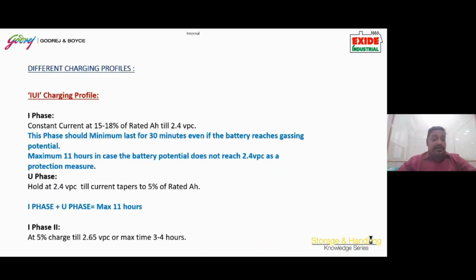Now, for the different charging profiles, one is the constant current. Constant current charges normally at 15 to 18% of the rated Ah till 2.4 VPC is achieved. So when I say that, I should charge the battery with 15% to 18% CC charging till 2.4. 2.4 VPC is 2.40 volt per cell. So normally the traction batteries can be charged up to 2.7, 2.8 volts per cell.